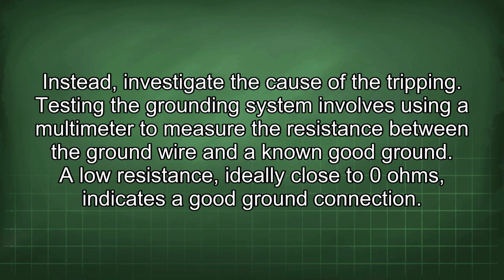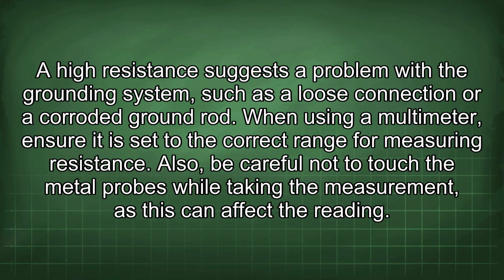Testing the grounding system involves using a multimeter to measure the resistance between the ground wire and a known good ground. A low resistance, ideally close to 0 ohms, indicates a good ground connection. A high resistance suggests a problem with the grounding system, such as a loose connection or a corroded ground rod. When using a multimeter, ensure it is set to the correct range for measuring resistance. Also, be careful not to touch the metal probes while taking the measurement, as this can affect the reading.